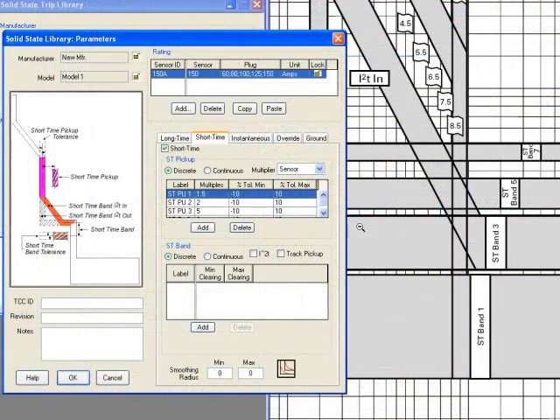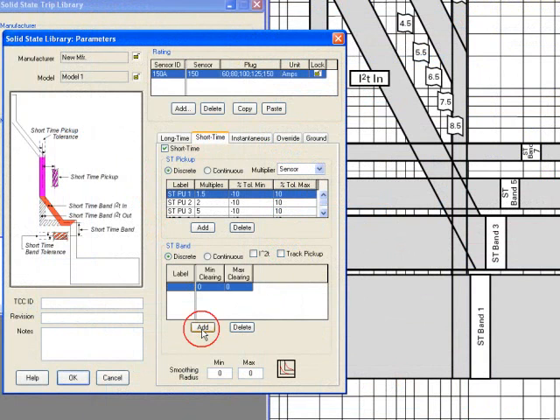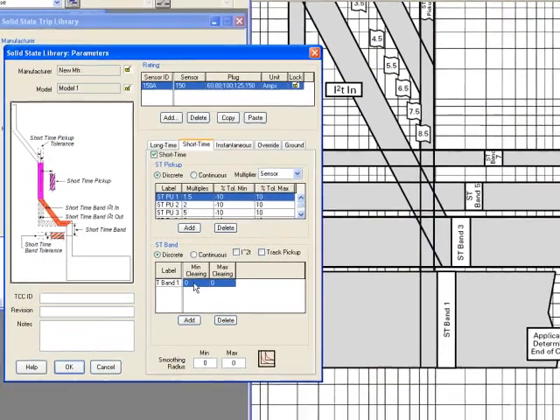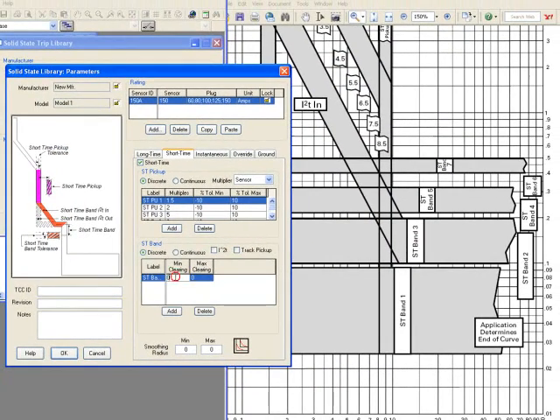You'll need to enter the Short Time band. Keep in mind the Short Time band can be entered as a horizontal shape and also as a slope shape, as an I squared T N, like in this case. The minimum clearing for Short Time band is 0.065, and the maximum clearing according to the manufacturer is 0.08.